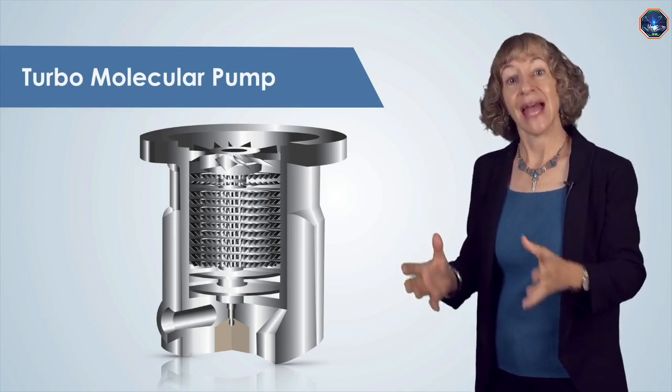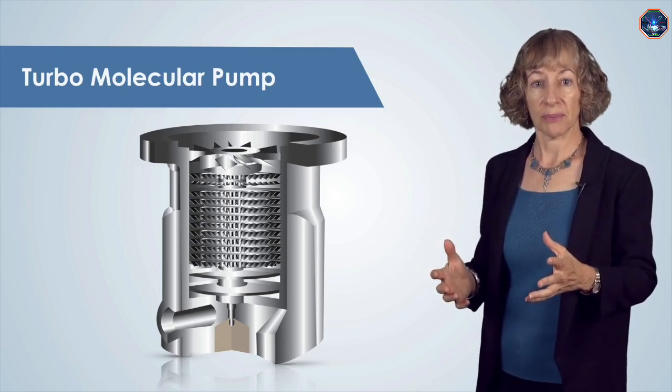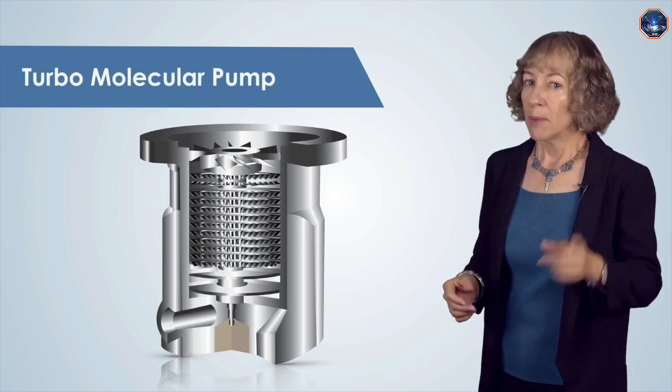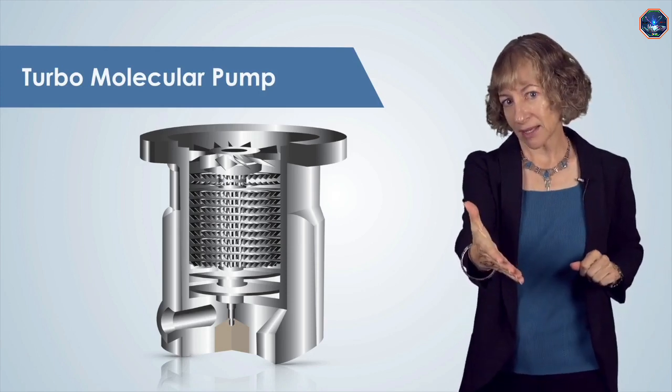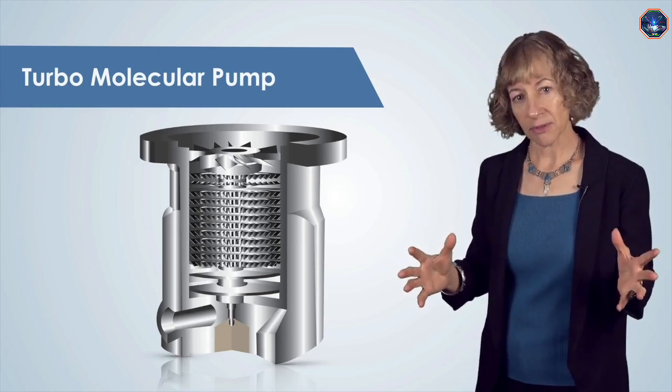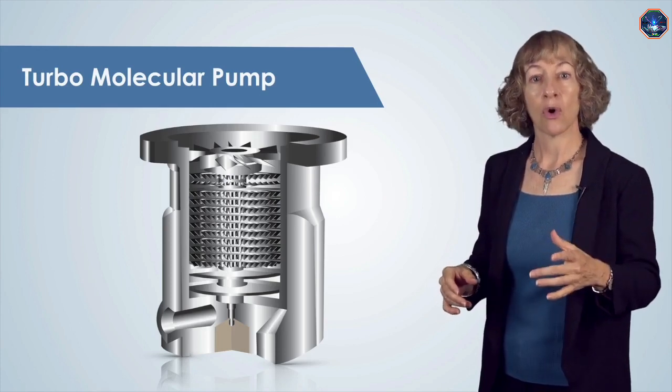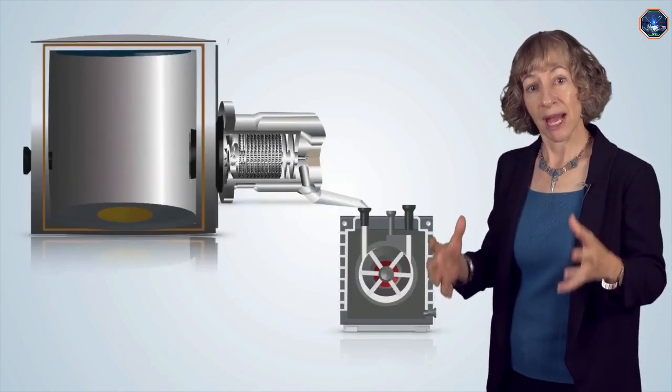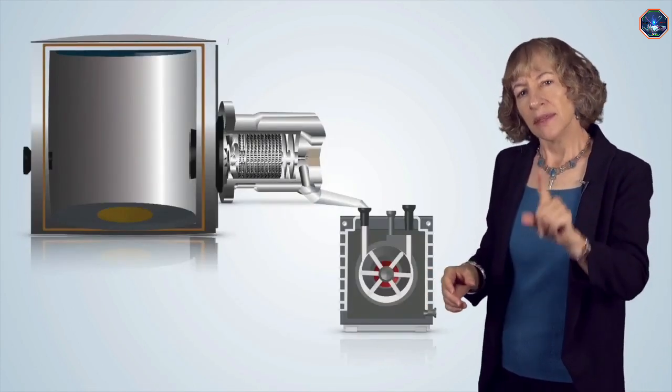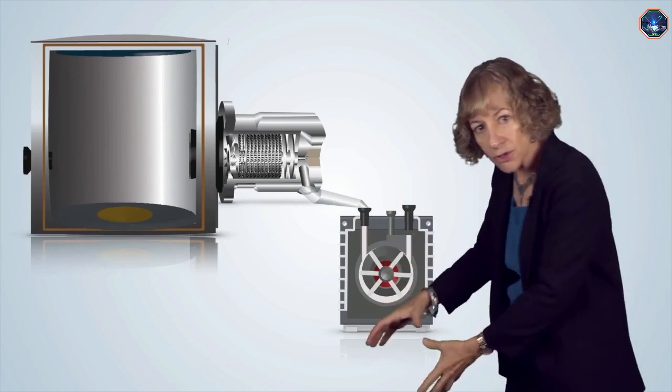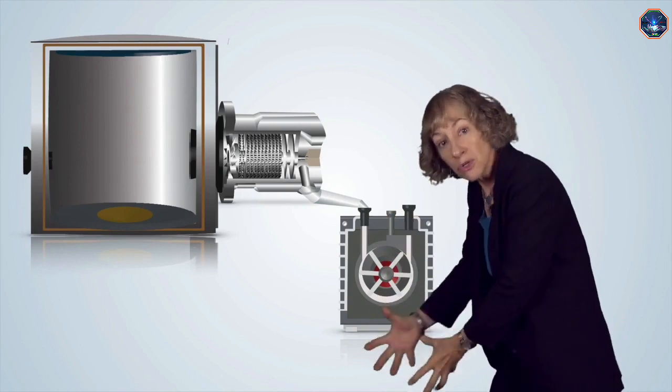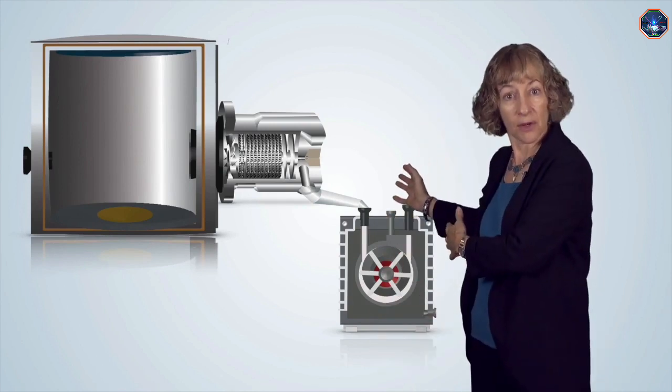First we rough pump the system with a mechanical pump, and then we use the turbo pump afterwards. But there is a catch: a turbo pump needs a helping hand—it cannot pump alone. It gets help, or we say is backed by, a mechanical pump. This simply means that the air from the output of the turbo pump is removed by the mechanical pump.